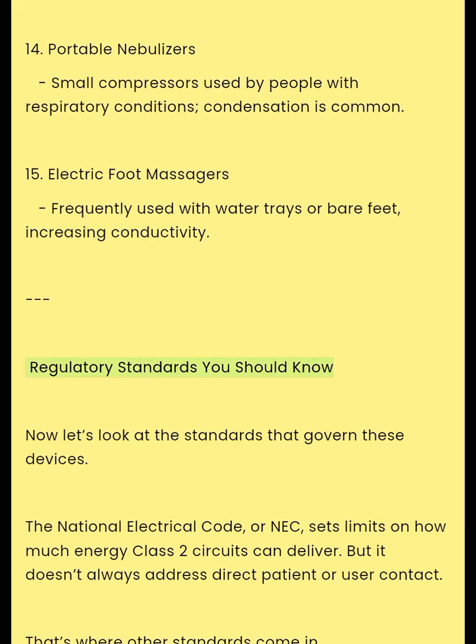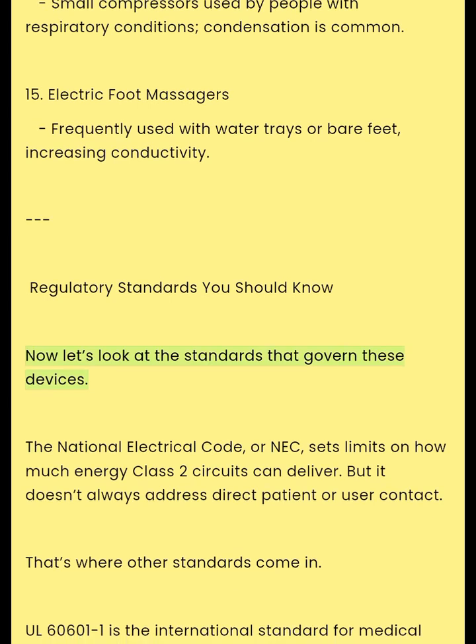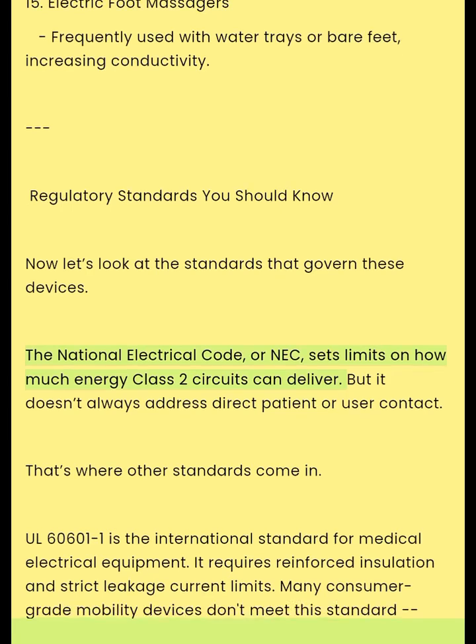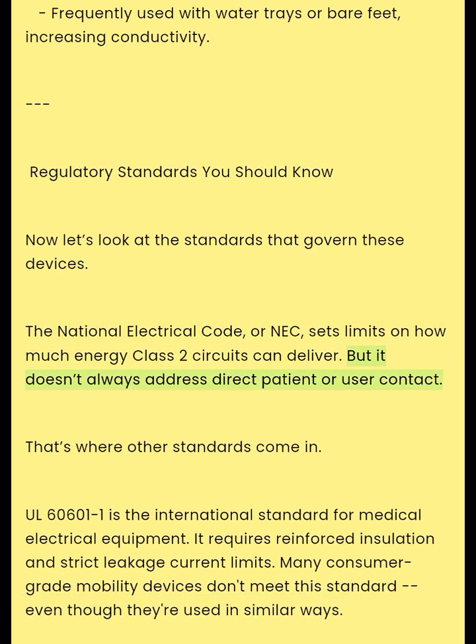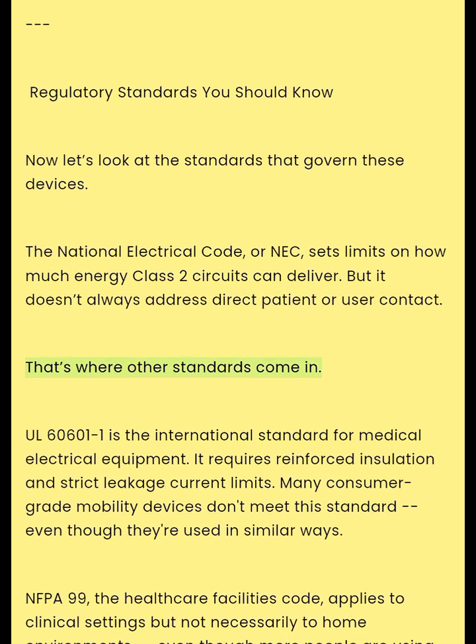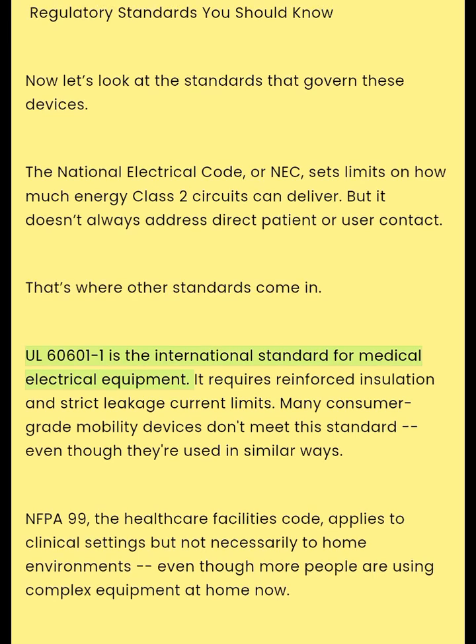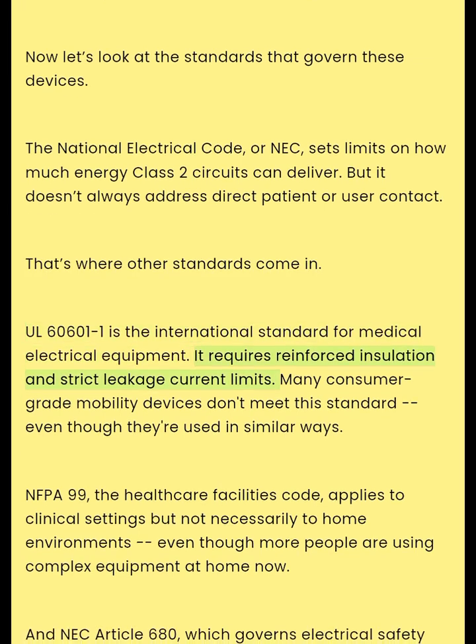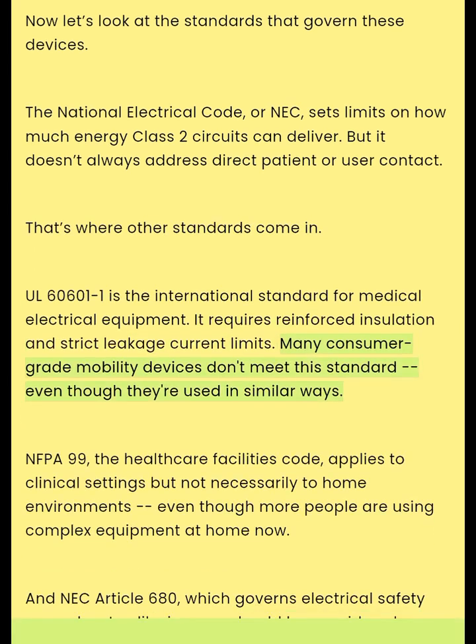Regulatory standards you should know. Now let's look at the standards that govern these devices. The National Electrical Code, or NEC, sets limits on how much energy Class II circuits can deliver. But it doesn't always address direct patient or user contact. That's where other standards come in. UL 60601-1 is the international standard for medical electrical equipment. It requires reinforced insulation and strict leakage current limits. Many consumer-grade mobility devices don't meet this standard, even though they're used in similar ways.